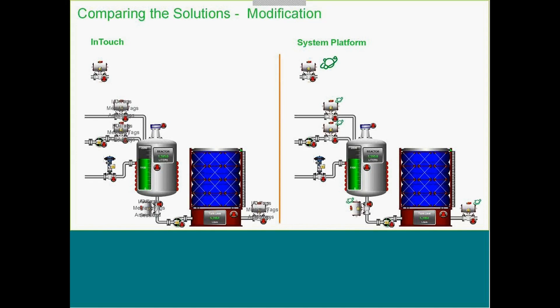If we need to modify our application in a tag-based solution, we have to go back and modify the various valves — adding functionality or extra condition monitoring. If you had to make that same change for all valves in the system, you have to change the tags, although graphics in newer versions of InTouch can be templatized to some degree. In System Platform, we edit our template, add the required functionality, and then propagate that change throughout all instances of our already-designed plant model, allowing for speedier deployment of functionality.